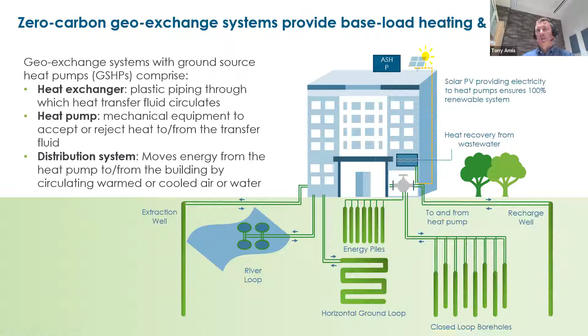One of the trickiest areas we've dealt with is whether to go decentralized or centralized with equipment. Involving the developer at this stage is very important, because their general design for typical buildings might be fan coil units or individual heat pumps in each unit. That will dictate the distribution system and can have a significant effect on the capital costs of the solution you're looking at.